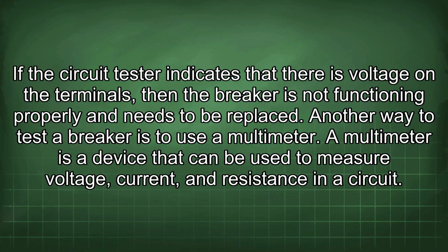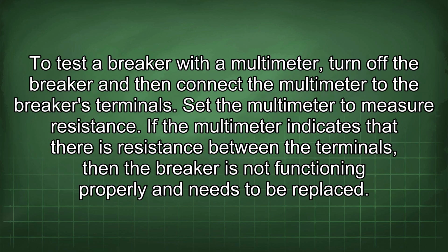Another way to test a breaker is to use a multimeter. A multimeter is a device that can be used to measure voltage, current, and resistance in a circuit. To test a breaker with the multimeter, turn off the breaker and then connect the multimeter to the breaker's terminals. Set the multimeter to measure resistance. If the multimeter indicates that there is resistance between the terminals, then the breaker is not functioning properly and needs to be replaced.